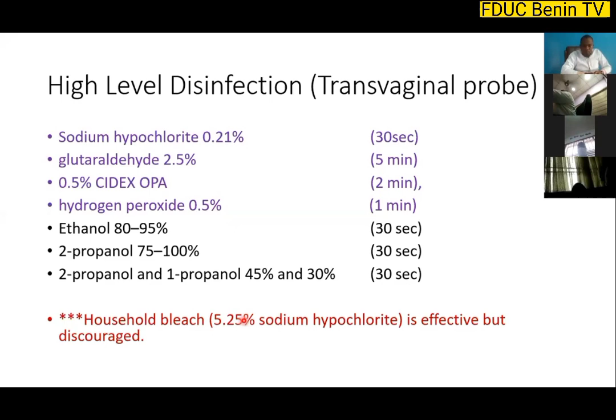Household bleach is the most readily available here, and that's why I'm talking about it. Please do not use household bleach because it is too concentrated for the materials used to make the probe and can readily damage it. When we have a suspected case, the best thing is to use a mobile scan and scan the patients in the room, a negative pressure room if possible, but we don't have negative pressure rooms in Nigeria. So avoid scanning COVID positive patients who need an ultrasound scan in the general purpose ultrasound room. The best thing is to have mobile scans and scan them at their bedsides.